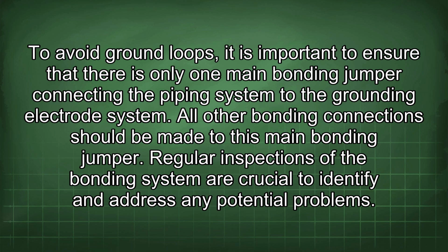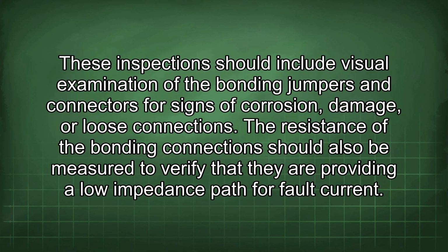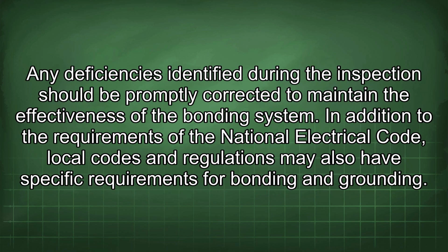Regular inspections of the bonding system are crucial to identify and address any potential problems. These inspections should include visual examination of the bonding jumpers and connectors for signs of corrosion, damage, or loose connections. The resistance of the bonding connection should also be measured to verify that they are providing a low impedance path for fault current. Any deficiencies identified during the inspection should be promptly corrected to maintain the effectiveness of the bonding system.